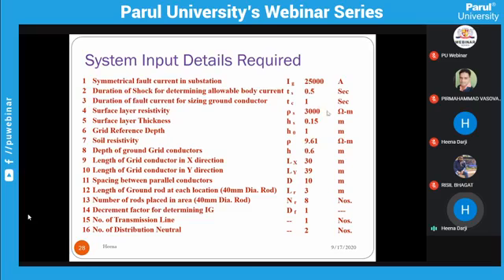Symmetrical fault current in substation. In all substations, meaning 400, 220 kV and 132 kV, your fault current is 31.5 kiloampere. Then in 110, 66 kV, 33 kV, your fault level is 25 kiloampere. So the fault level is different, depending upon your kV. So this is 25 kiloampere.